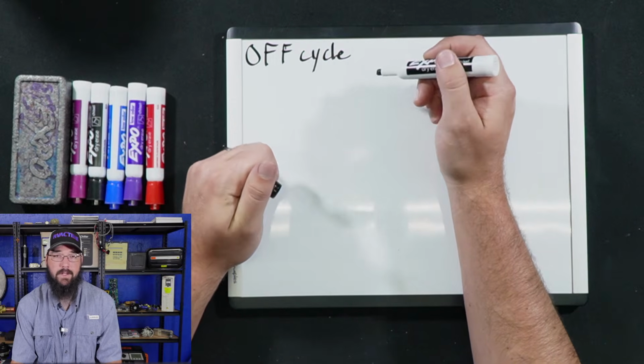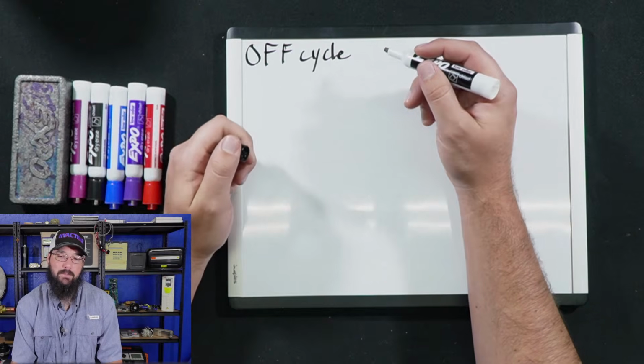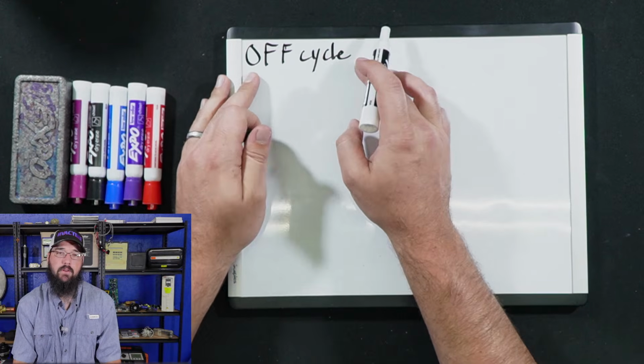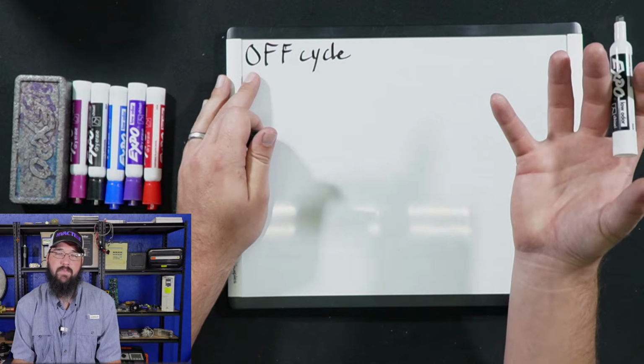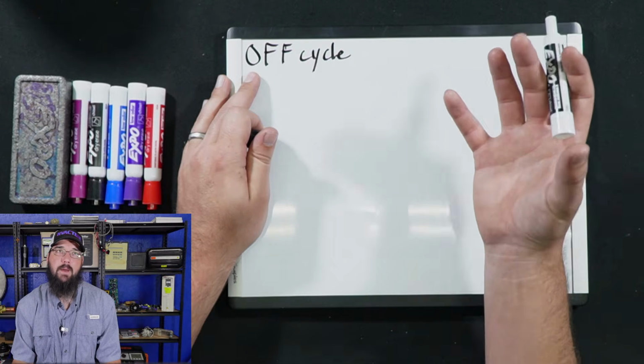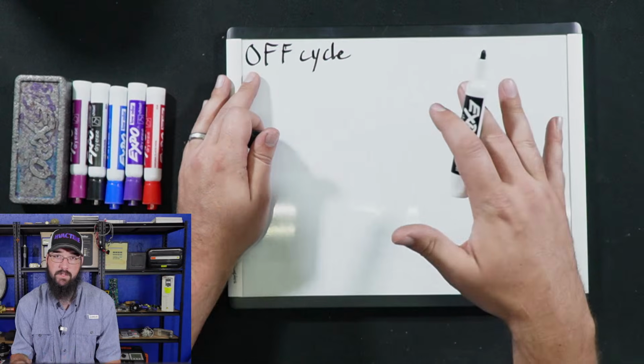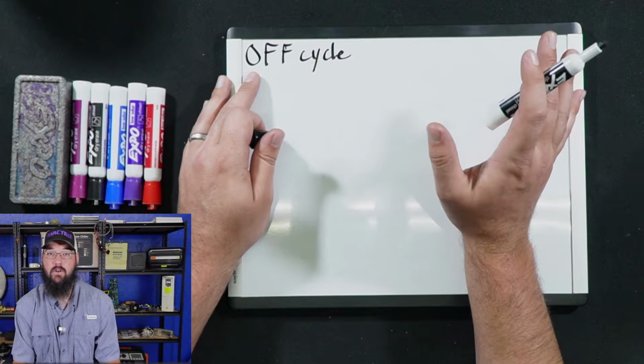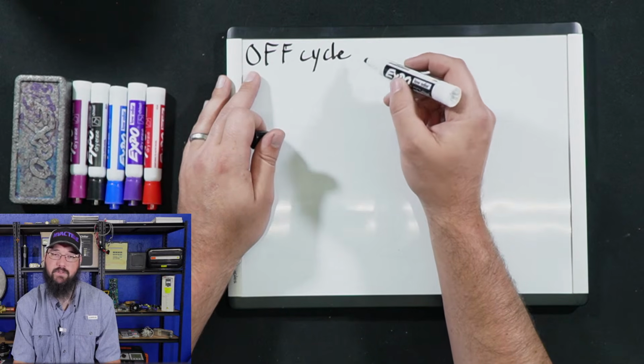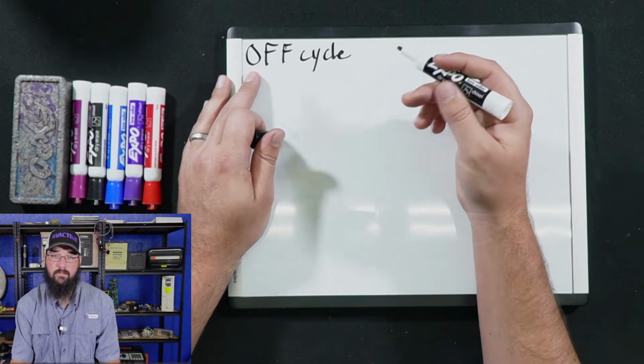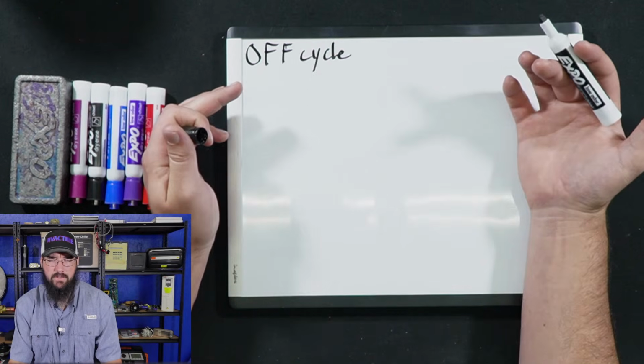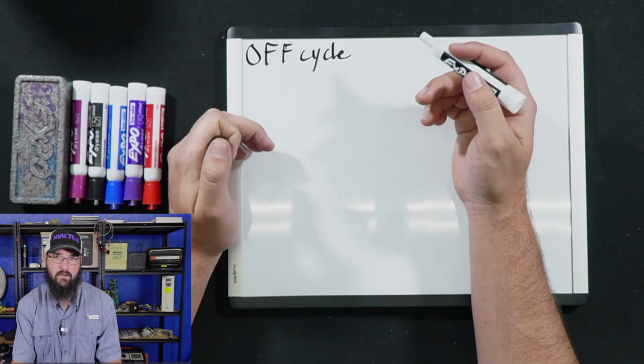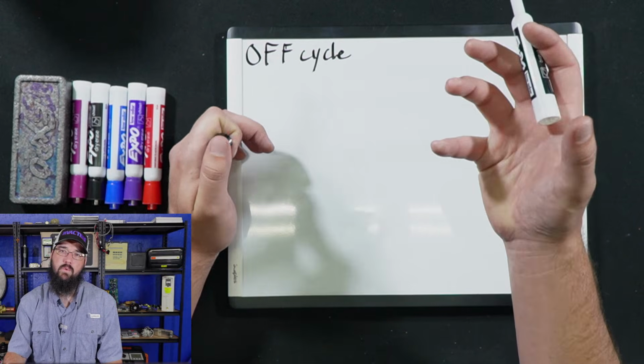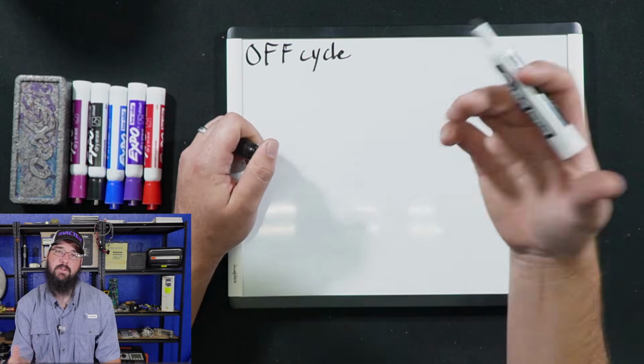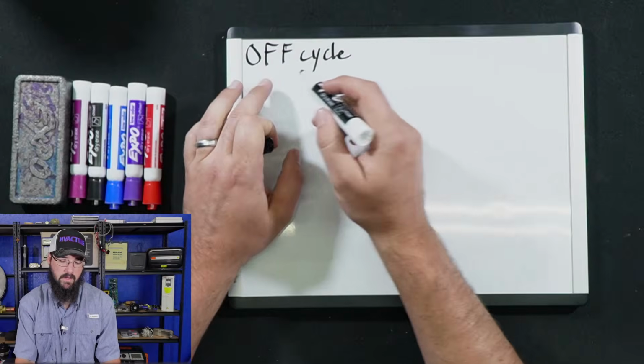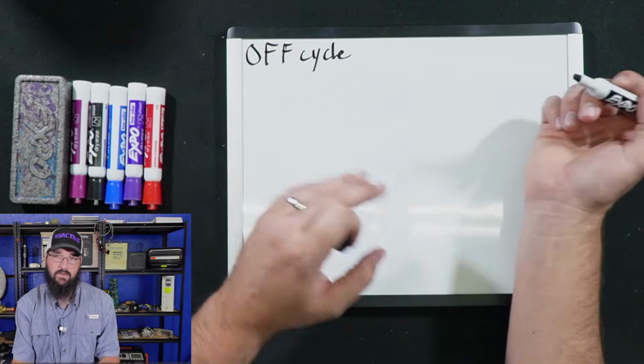One that's really bad about this is an RTHD, sadly, by Trane. They're notorious for it in the off cycle, especially if you don't have your evaporator isolated in off cycle. If that machine is off, that evaporator cannot have flow through it at all. I've had that happen with machines where they get just a little tiny trickle, which for a lot of machines isn't that big a deal, but these RTHDs really struggle with it. The ISO valve for flow doesn't 100% stop, and it's just a teeny little trickle, but it's just enough to keep the evaporator cold in the off cycle, and it just sucks that oil right out of the sump.